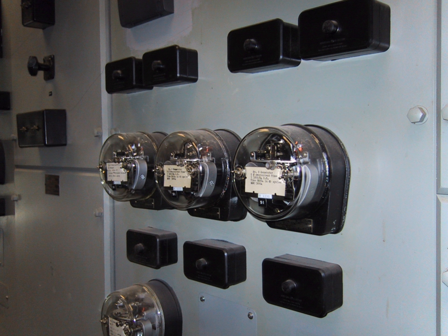The time taken for rotation to make the contacts is not only dependent on current but also the spindle backstop position, known as the time multiplier. The time multiplier is divided into 10 linear divisions of the full rotation time. Providing the relay is free from dirt, the metal disc and the spindle with its contact will reach the fixed contact, thus sending a signal to trip and isolate the circuit, within its designed time and current specifications.